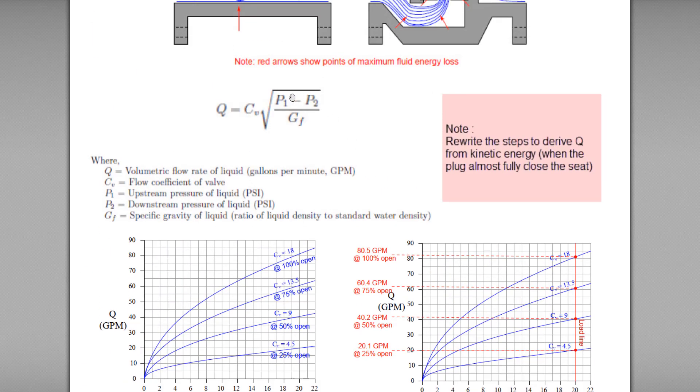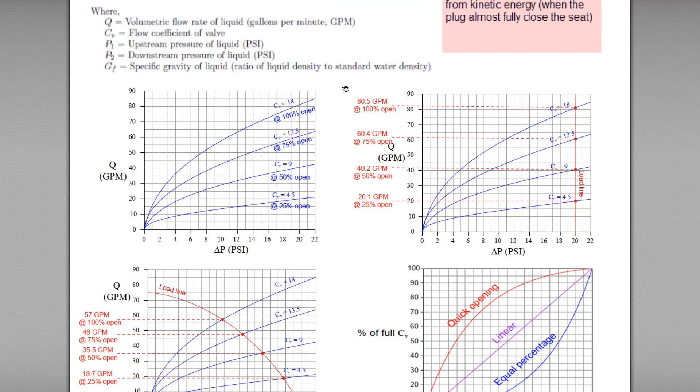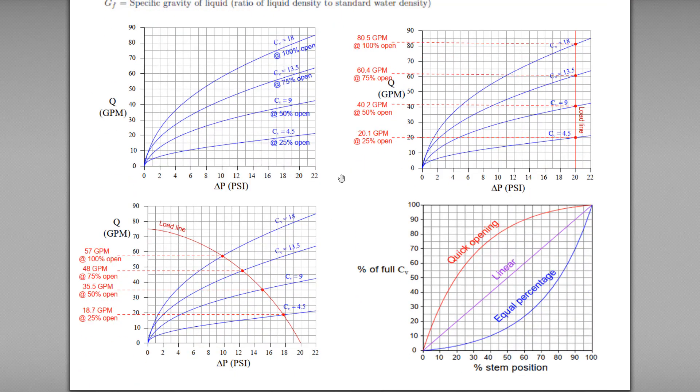Let's say this differential pressure is variable, is changing. So what will the curve look like? For example, if the differential pressure is 18 psi, according to this curve, you notice that the CV is about 4.5 at 25% valve opening. The corresponding flow rate will be 18.7 gallons per minute.